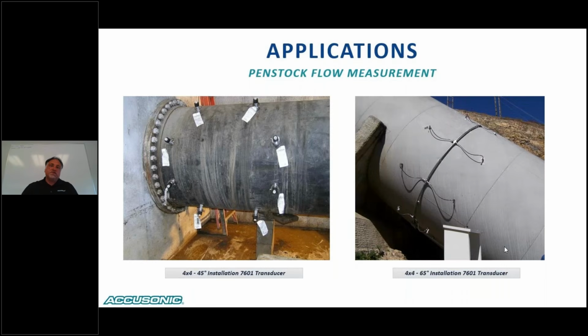This picture shows the difference between a feed-through style transducer that's installed at a 45-degree path angle and one that's installed at a 65-degree path angle. The one on the right is a very large diameter penstock. I believe it's about 6.5 meters in diameter. So we utilize a 65-degree plane to shorten up the axial distance and reduce the path length value, which will increase the signal strength of the transducers.